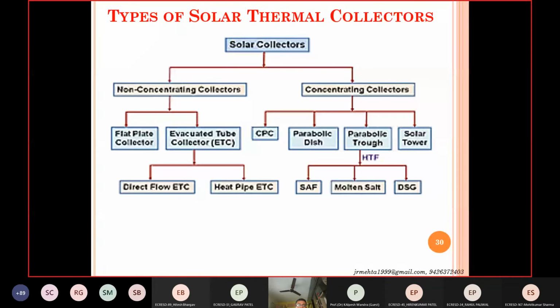and then the cold can be delivered into the building. So what are the different types of solar thermal collectors available? The flat plate collector or evacuated tube collector. Again, you can have direct flow and heat pipe in this ETC. Concentrating collectors. So when you want higher temperatures, one should go for concentrating collectors. If low temperatures are good enough for you, you should not adopt concentrating collectors because they are costlier, they are more complex to operate. Right, so the concentrating collectors, CPC, parabolic dish, parabolic trough, solar tower, and again different systems in parabolic trough, different technologies also.